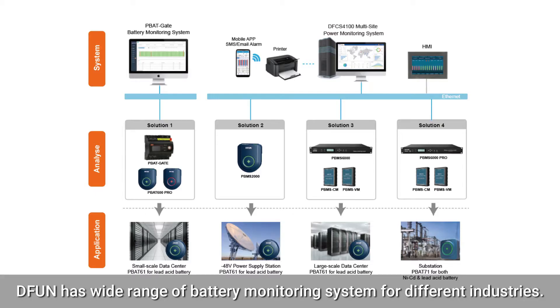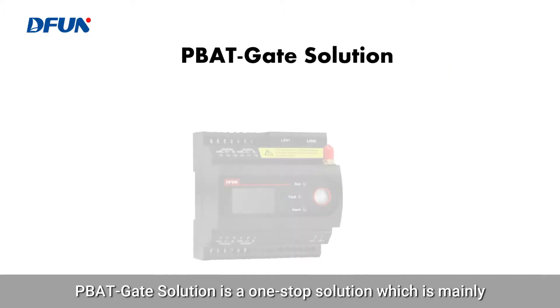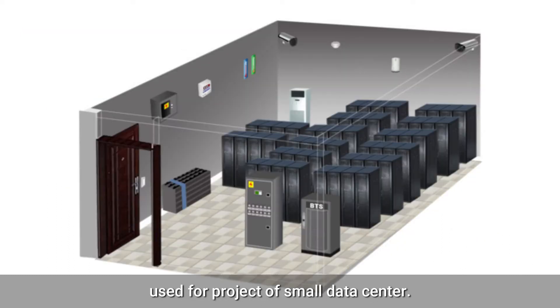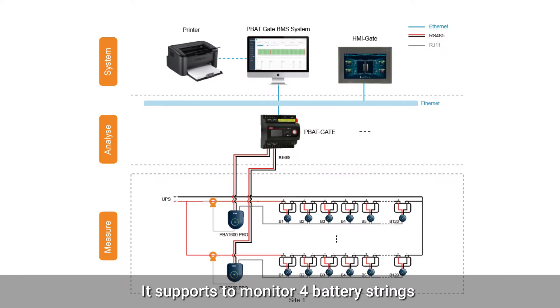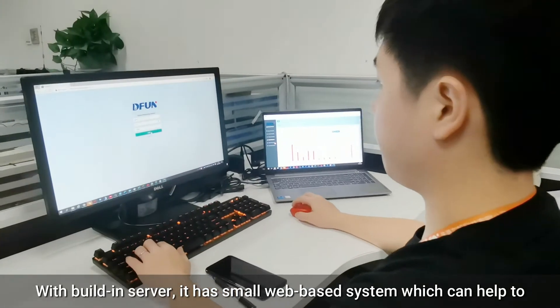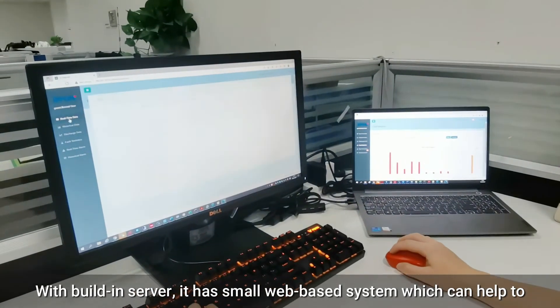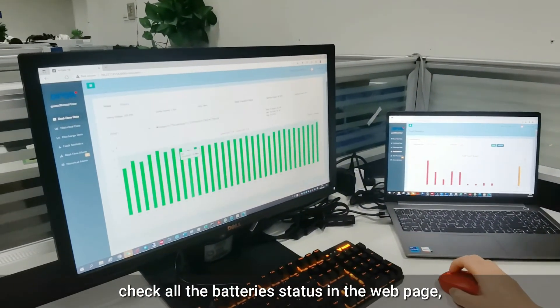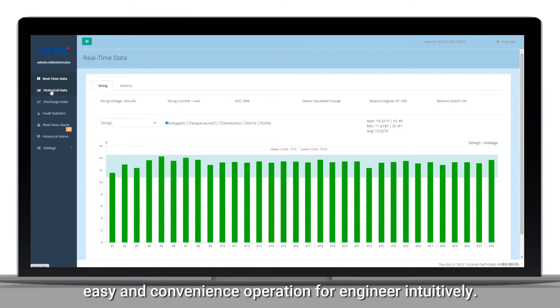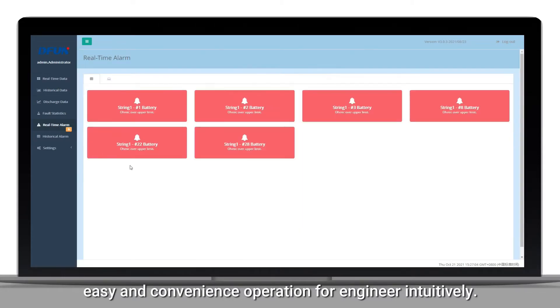DFUN has a wide range of battery monitoring systems for different industries. The PBAT-Gate solution is a one-stop solution which is mainly used for projects of small data centers. It supports monitoring for four battery strings and 480 pieces of lead-acid batteries in total. With a built-in server, it has a web-based system which can help check all the battery status on a web page — easy and convenient operation for engineers intuitively.